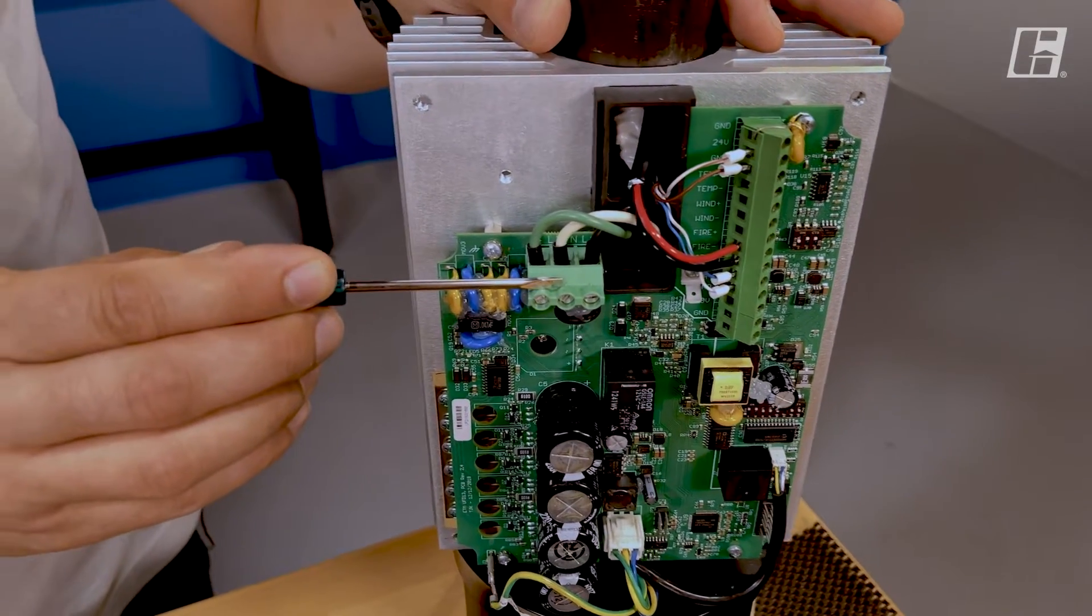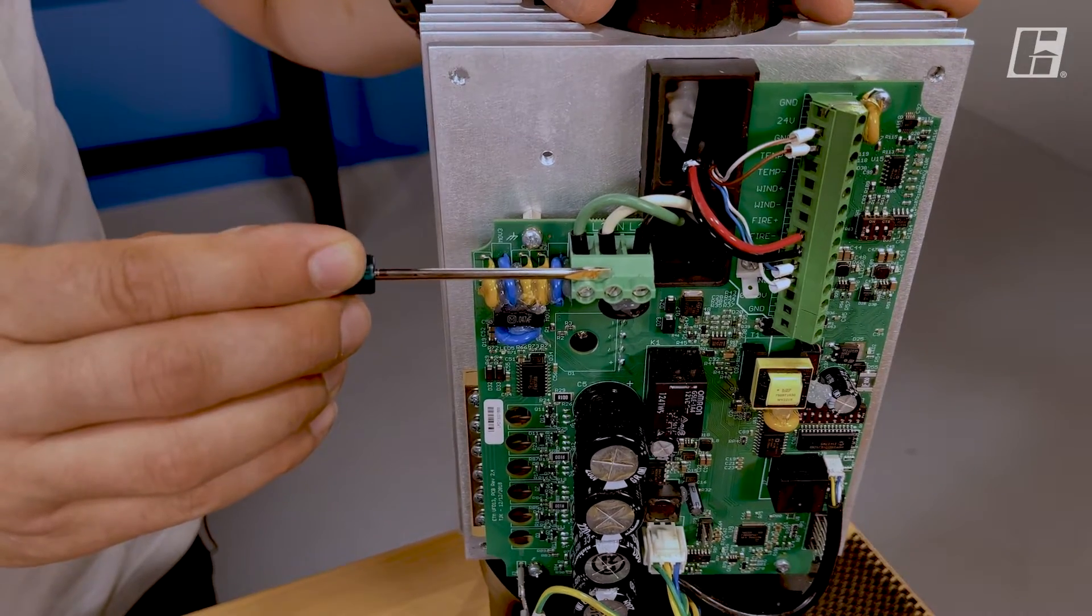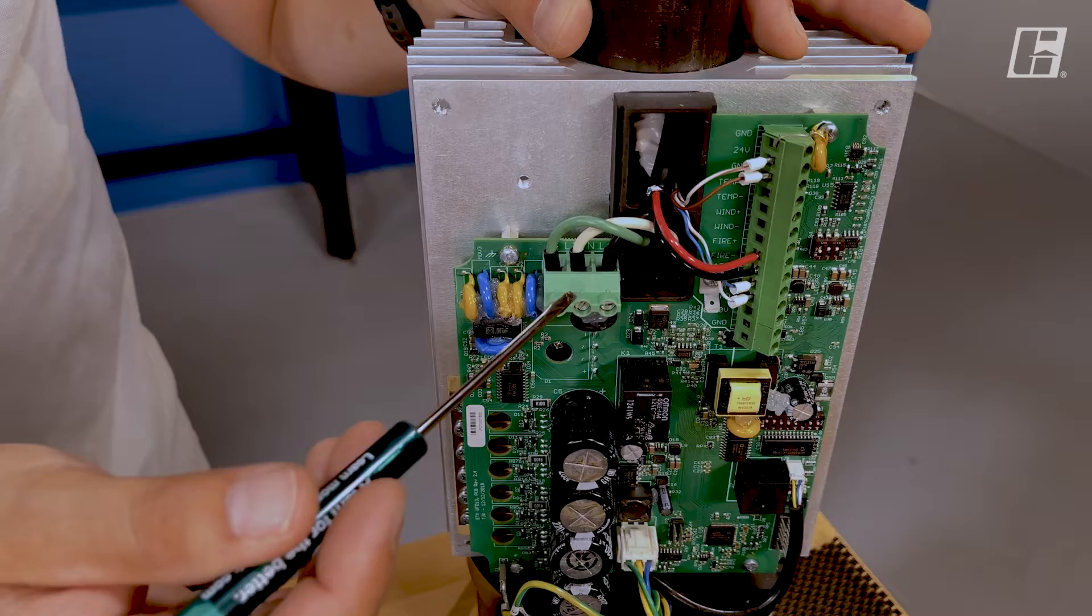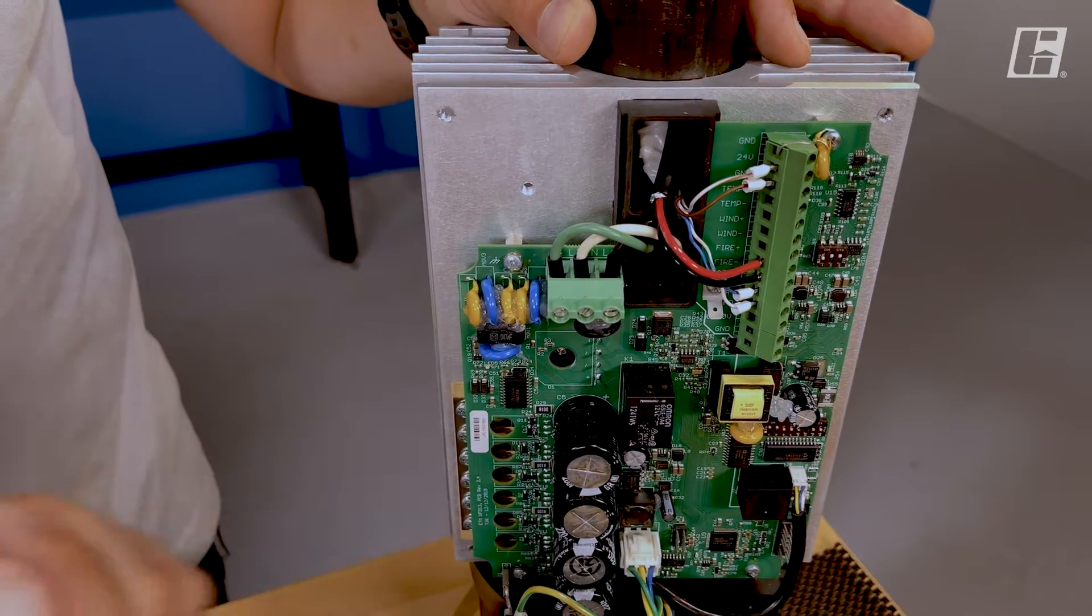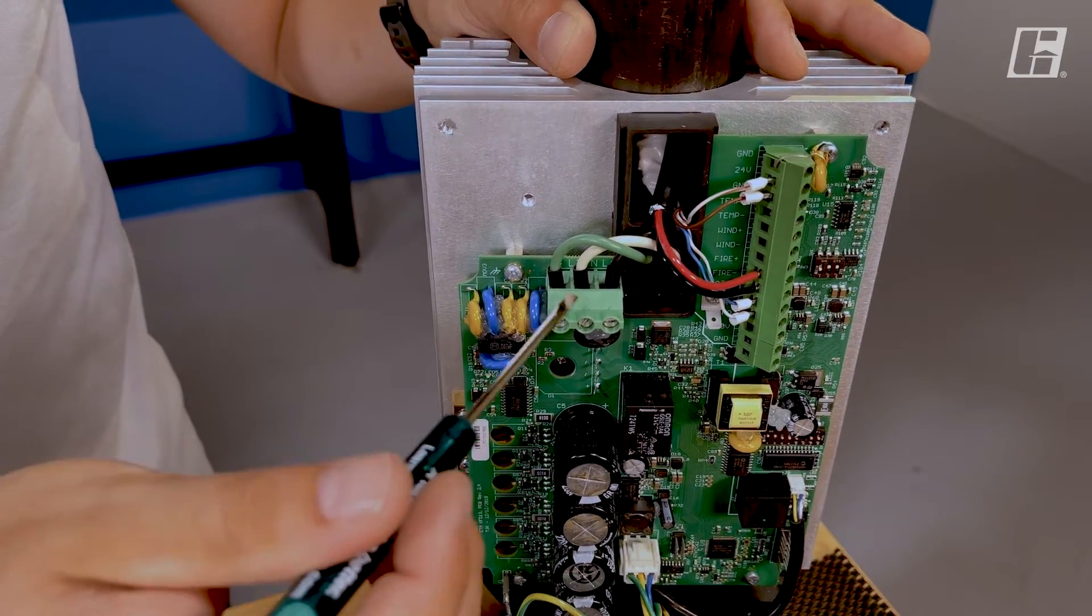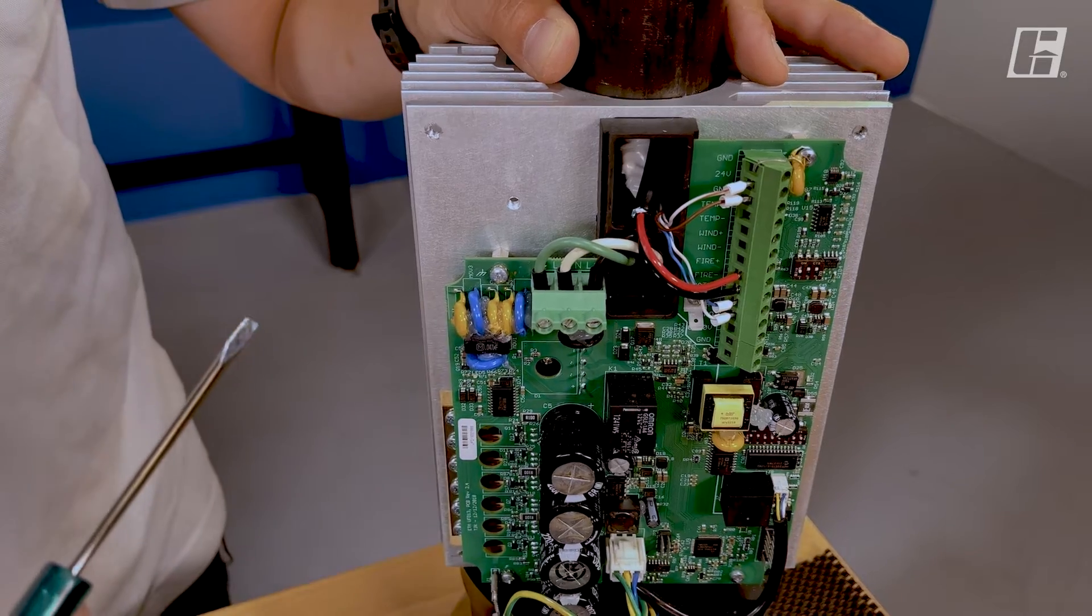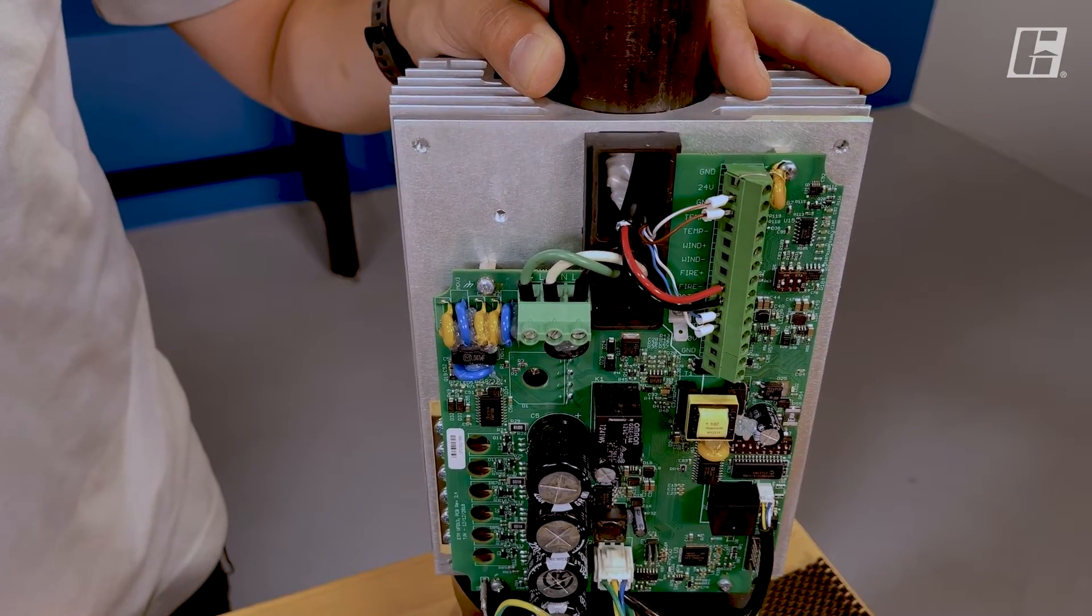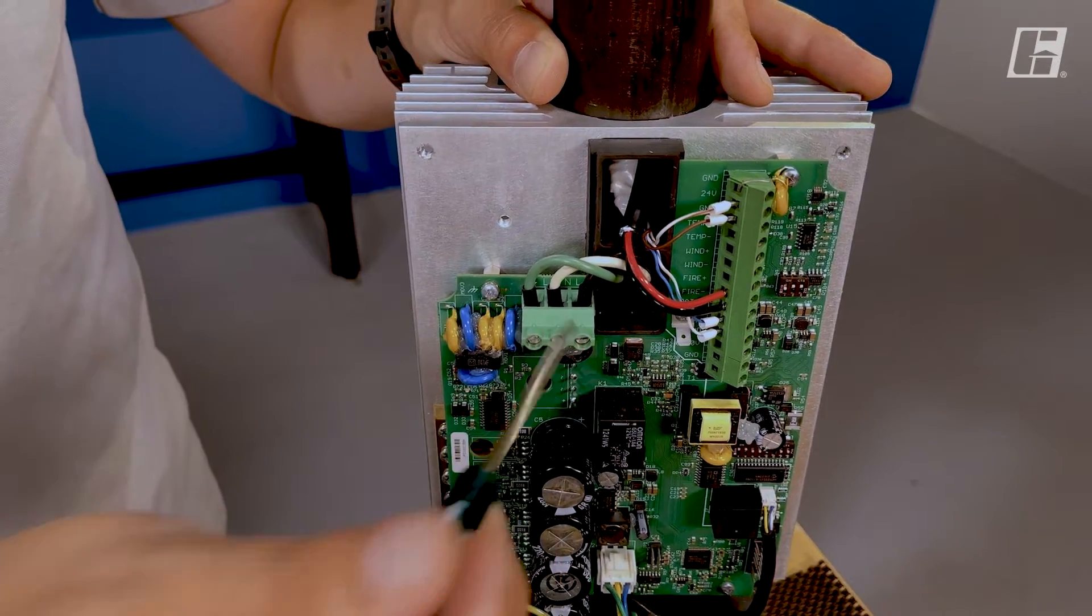Here we have our high voltage input. This can take single phase 110 or 220 power. We've got our ground, one leg of voltage, and the other. It does not matter if this is neutral and this is L1, or if this is L1 and this is neutral. Similarly with 240, the inputs do not matter.